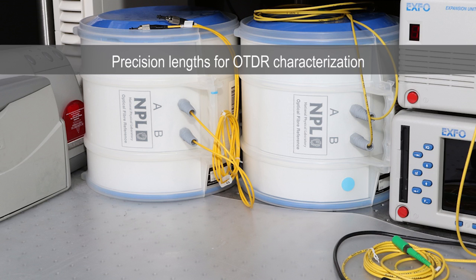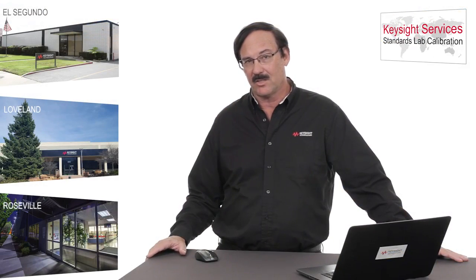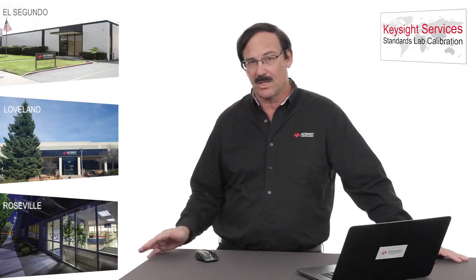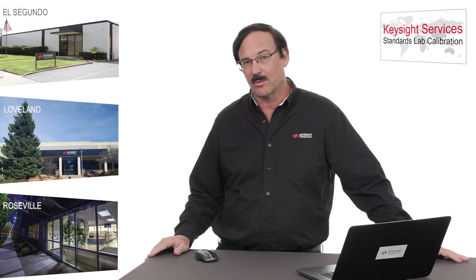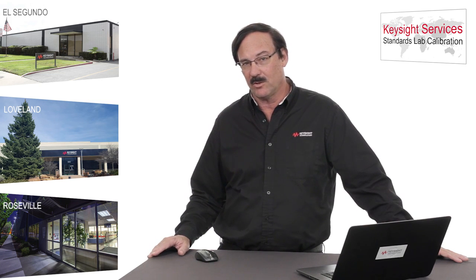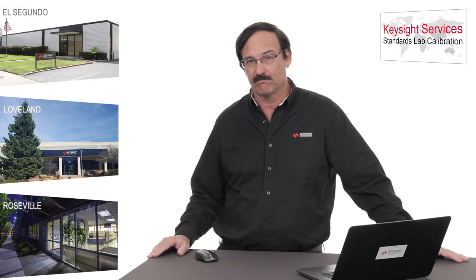This one's coming from UKNPL. We have two lengths. I think one of them is 13 kilometers and the other one is 5.6 kilometers. These are for use in calibrating optical time domain reflectometers, or so-called OTDRs. And the idea here is that the distance to the discontinuity, which is the end of the cable, is very accurately known. Therefore, you can use this to calibrate your OTDR.